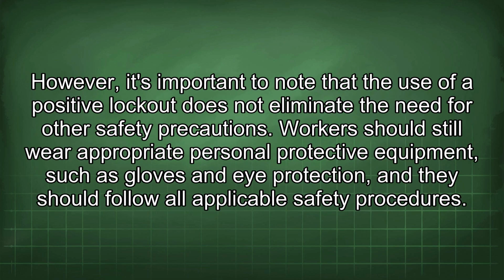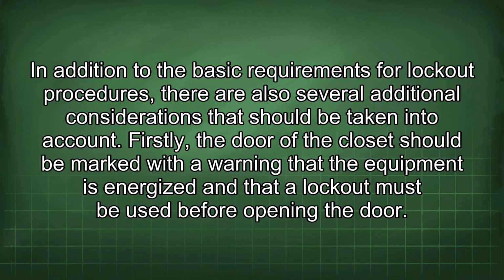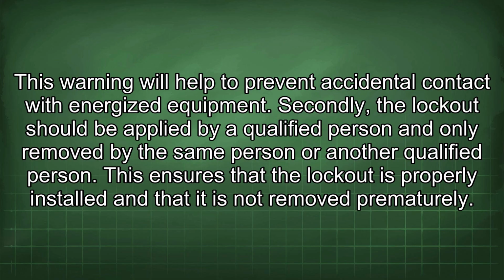However, it's important to note that the use of a positive lockout does not eliminate the need for other safety precautions. Workers should still wear appropriate personal protective equipment such as gloves and eye protection, and they should follow all applicable safety procedures. In addition to the basic requirements for lockout procedures, there are also several additional considerations that should be taken into account. Firstly, the door of the closet should be marked with a warning that the equipment is energized and that a lockout must be used before opening the door. This warning will help to prevent accidental contact with energized equipment.